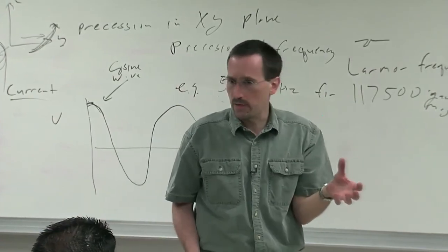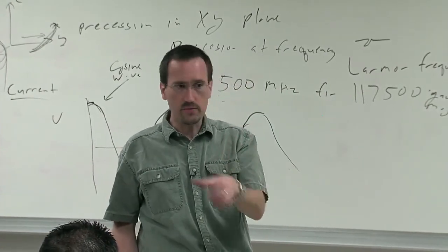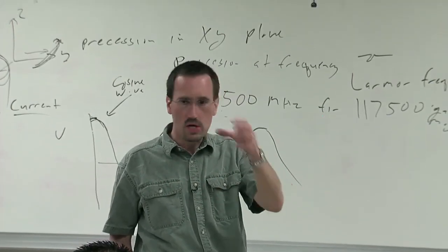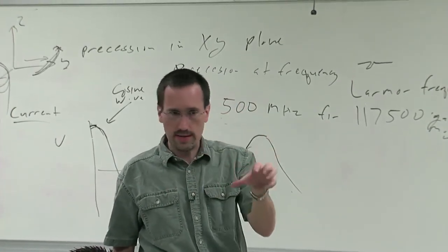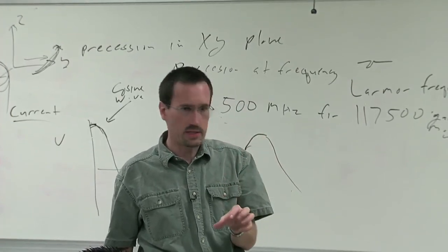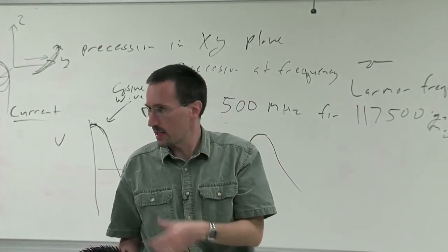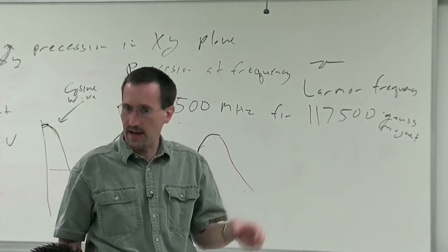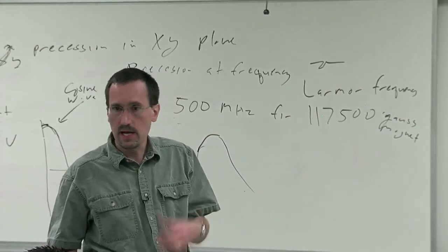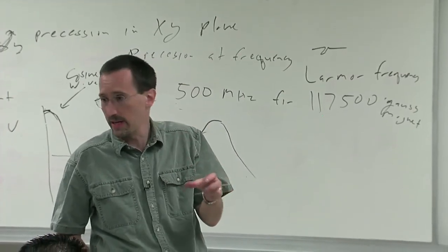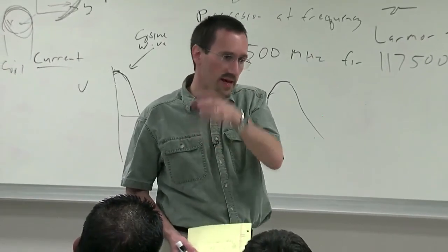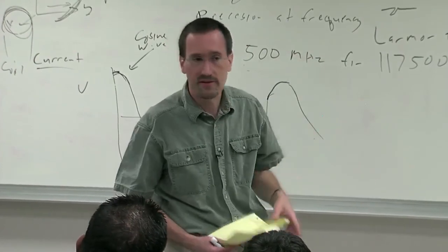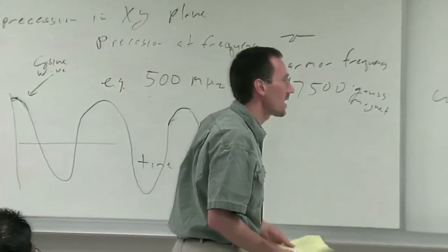That comes back to what I was saying before about, remember I mentioned broadband detection and the proton coil? So in general, different coil shapes work well for different frequencies. And so one coil's on the inside. So if we are doing proton NMR, it's best to have your proton coil on the inside. If you're trying to get the best carbon NMR, in general, it's best to have a coil tuned to carbon's frequency. Remember, they differ by a factor of 4 on the inside.